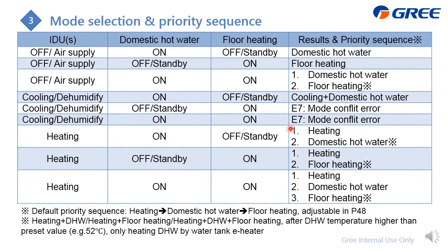The last is the mode selection and priority sequence, which means either the indoor unit is off, air supply, cooling, dehumidifying, or heating, and the DHW is on, off, standby, floor heating on, off, standby. And with this combination, what are the results? And what is the priority sequence? I just made this table for your reference to memorize more easily, with this combination, which the system will do first, and then second, and the last. Also the default priority sequence will be heating, and after that DHW, and the third is the floor heating. It is adjustable in P48.